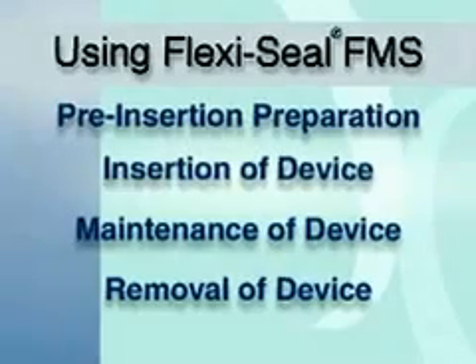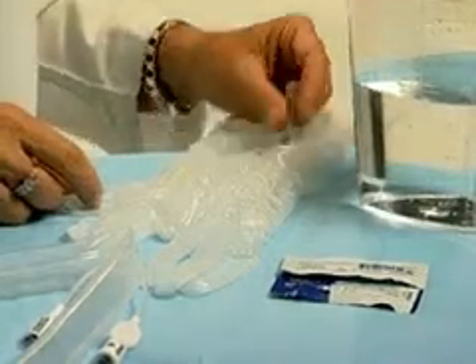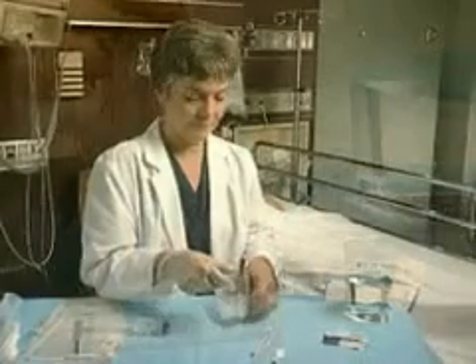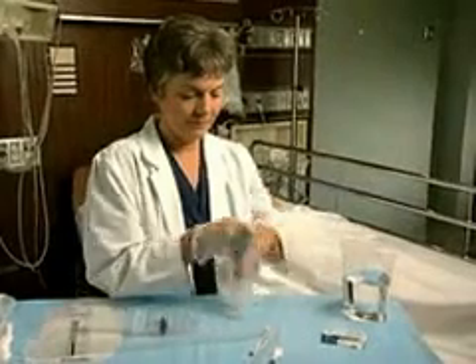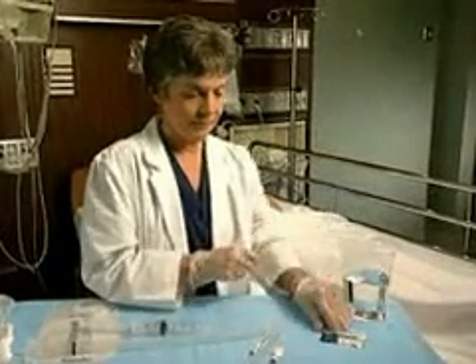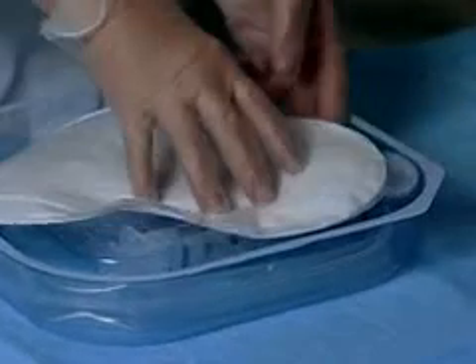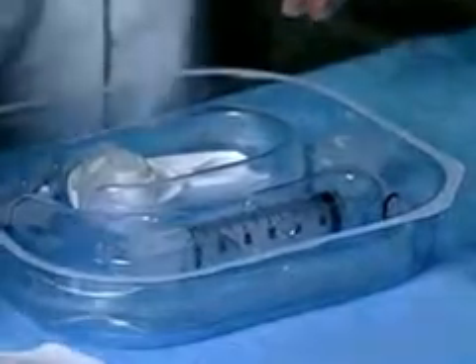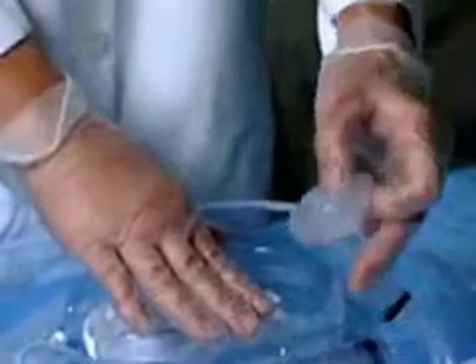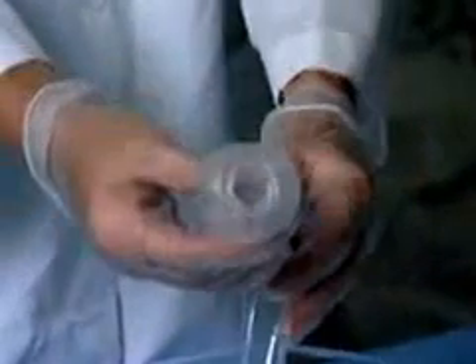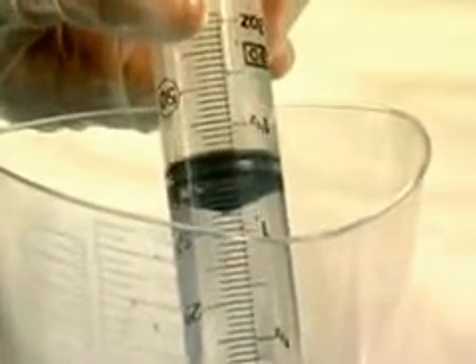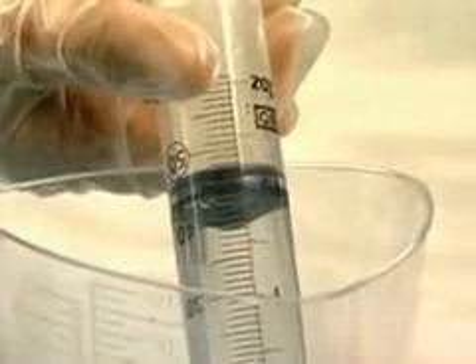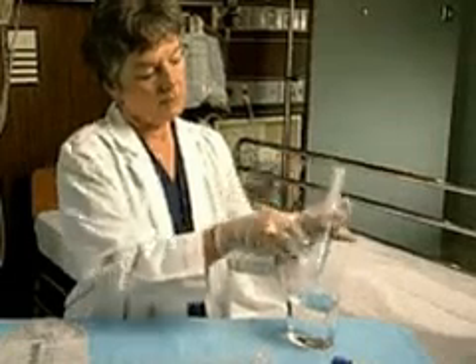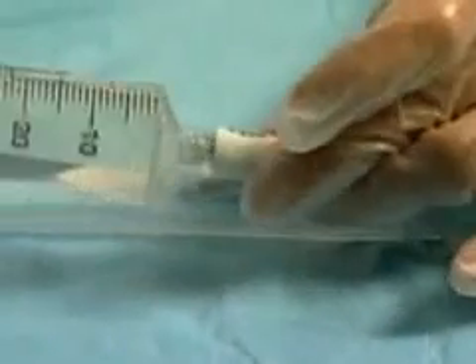In addition to the device kit, you will need gloves and a lubricant. You should perform a digital rectal exam to ensure that there is no fecal impaction. When removing the device from the packaging, check to see if there is any air in the balloon. If so, remove the air by using the syringe. Next, fill the syringe with 45 milliliters of tap water or saline and attach it to the inflation port.